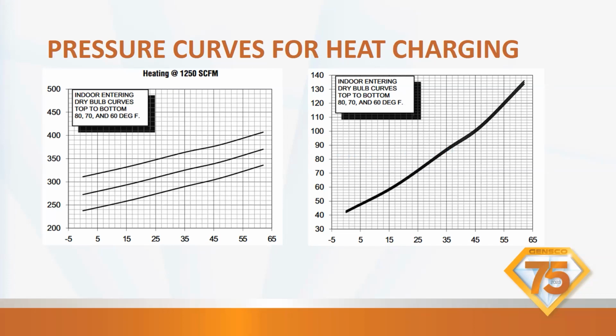So again, outdoor, indoor, straight across to the pressure you want. If you're below the line, you're going to add refrigerant. If you're above the line, you're going to take refrigerant out, and that's on the high side one. The low side's for reference. The high side, that's what we're charging to, because those are basically the subcooling charts in heat pump mode. Okay.